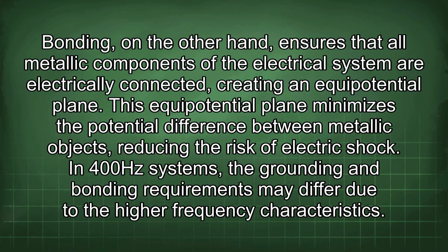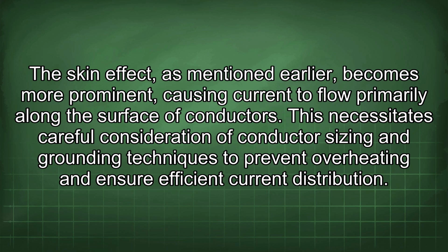In 400Hz systems, the grounding and bonding requirements may differ due to the higher frequency characteristics. The skin effect, as mentioned earlier, becomes more prominent, causing current to flow primarily along the surface of conductors. This necessitates careful consideration of conductor sizing and grounding techniques to prevent overheating and ensure efficient current distribution.